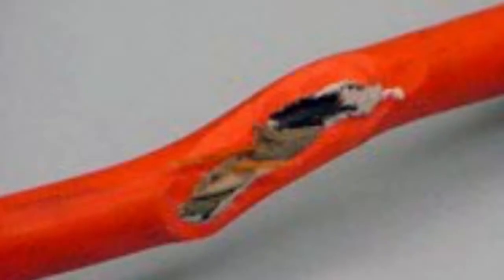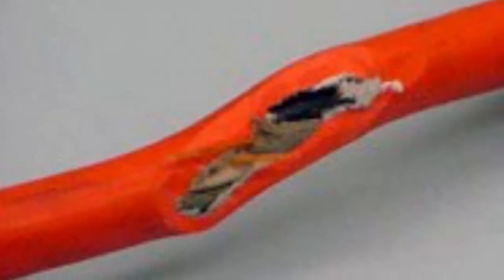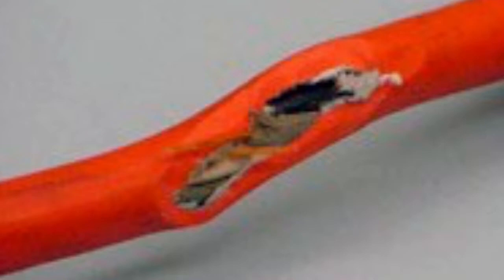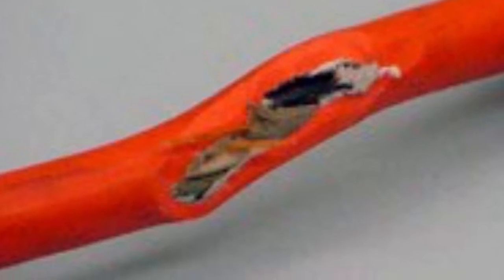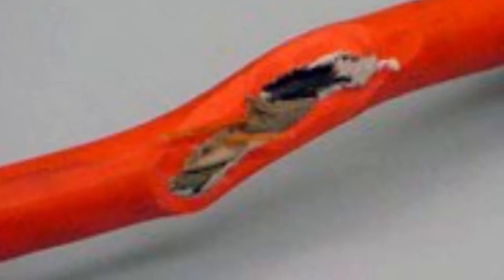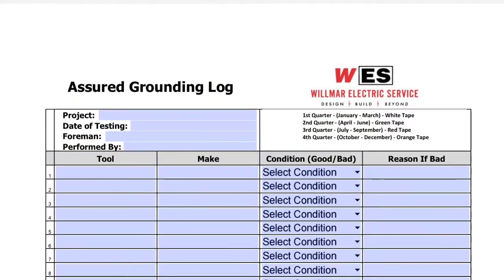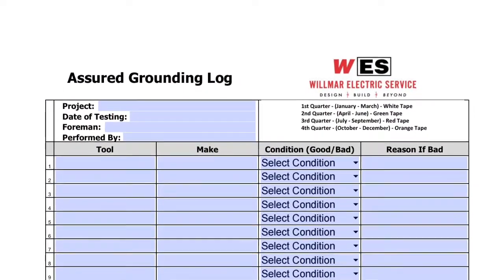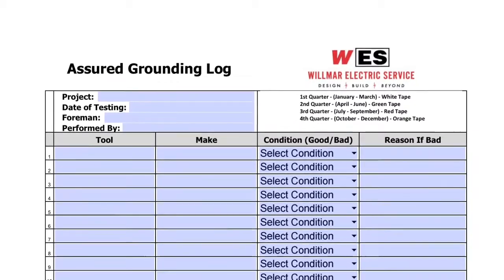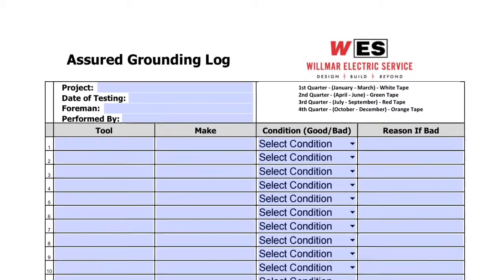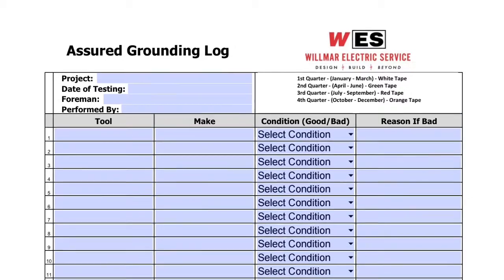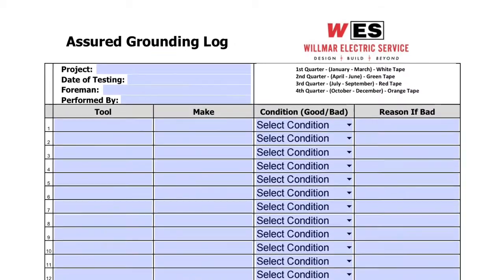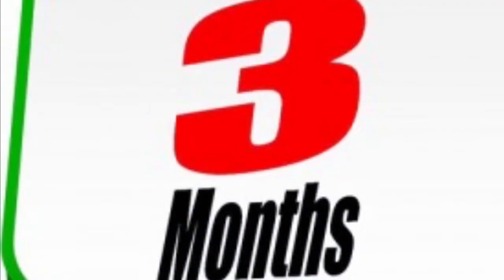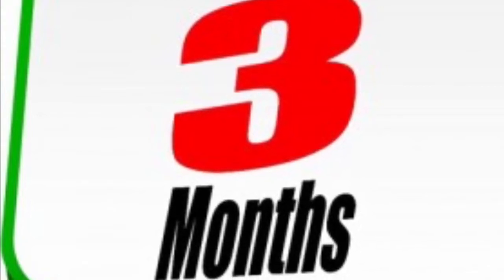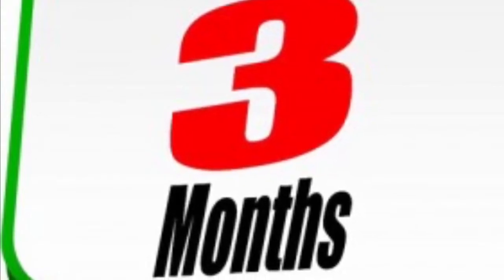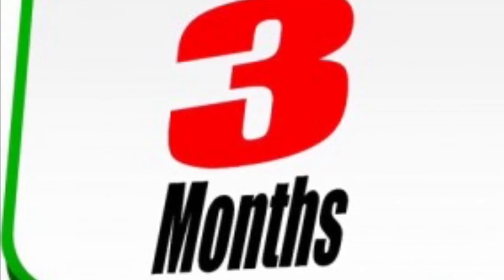Equipment must be visually inspected for damage and defects before each day's use. The test must be performed before the first use of new equipment, after suspected damage to equipment, and at 3-month intervals. When testing tools and equipment, an assured grounding log must be completed and submitted by a competent person who knows how to correctly test the tools and equipment. Once submitted, all assured grounding logs are stored digitally to the job using Procore. The assured grounding log must be conducted and submitted every 3 months. The assured grounding log can be found in the Safety Reference Job on Procore.